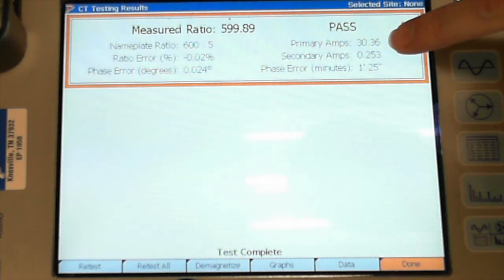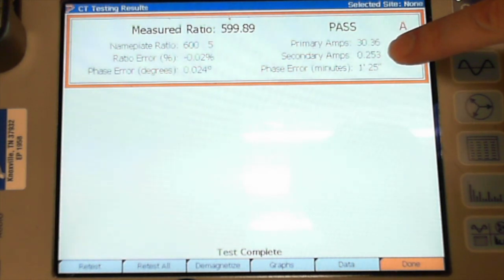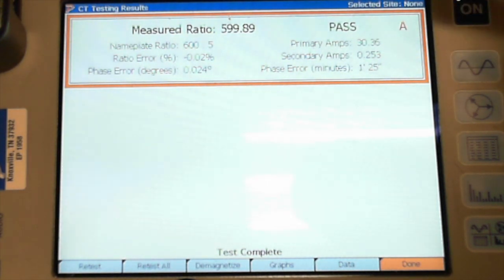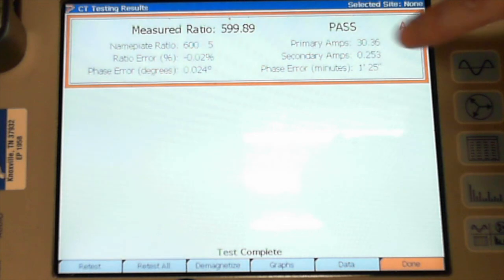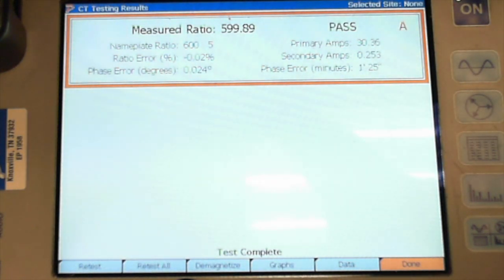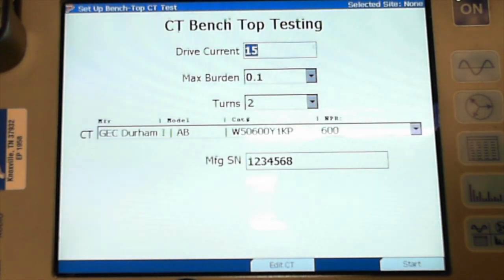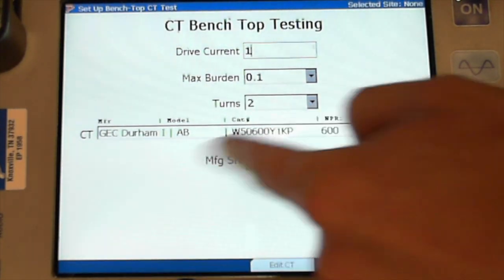So this is what I'm driving. I drove 30 amps, and then I measure about a quarter amp on the secondary side. So 30 amps is right about 5% of the CT itself. So I was telling Nick this, I'm very curious what happens if I drop it below the 5% range. How does it look? So let's go back and let's drop this down to 10 amps.